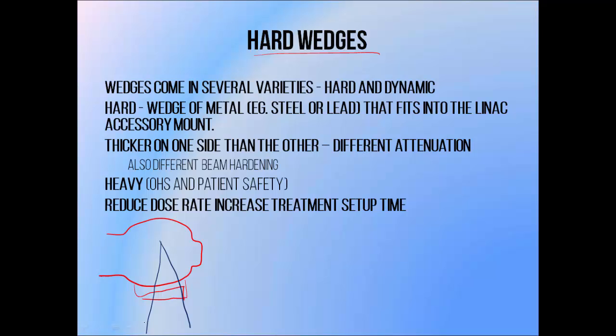Hard wedges have to be inserted manually, and the same wedge is often not required for every beam in a patient treatment. So it requires a lot of trips in and out of a treatment room during delivery, which can extend treatment times. Because these wedges are quite heavy, being made of thick pieces of metal, they can pose an occupational health and safety risk to both staff and patients. Also, because we're passing the beam through an additional layer of filtration, it does reduce the dose rate.